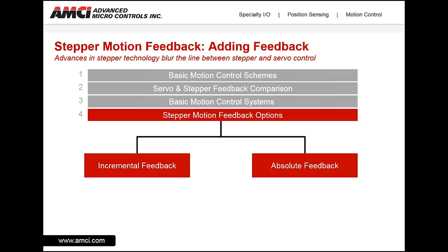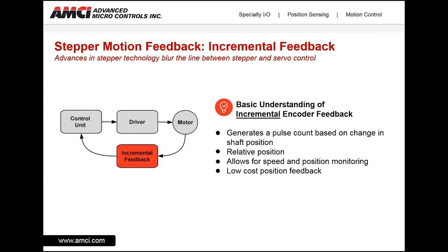Let's start by looking at incremental feedback with steppers. An incremental encoder generates a pulse count based on a change in shaft position. This change is referred to as relative position — it does not tell the user where it is, but how far it has traveled since the last position. Incremental encoders are a good choice for applications that require speed monitoring as well as position monitoring, and carry a lower cost when compared to absolute position feedback.